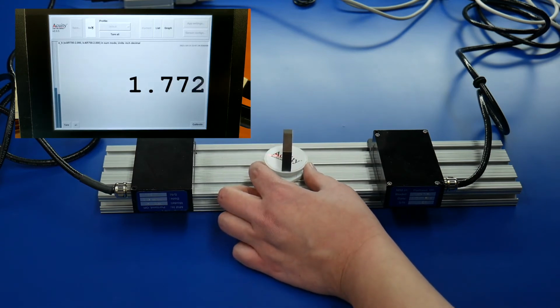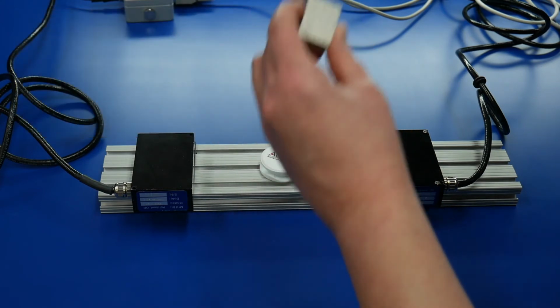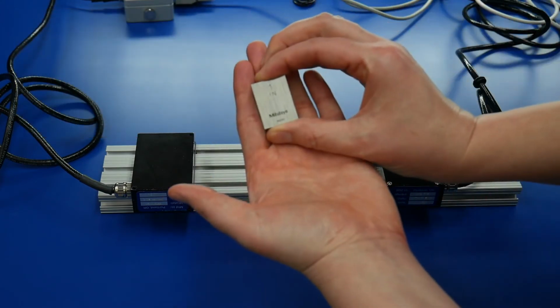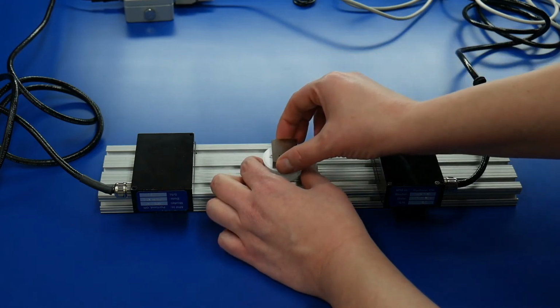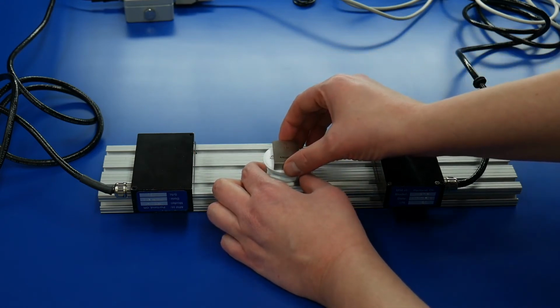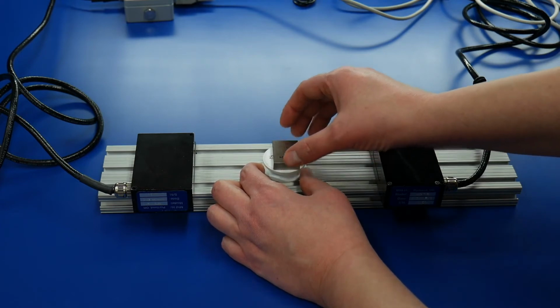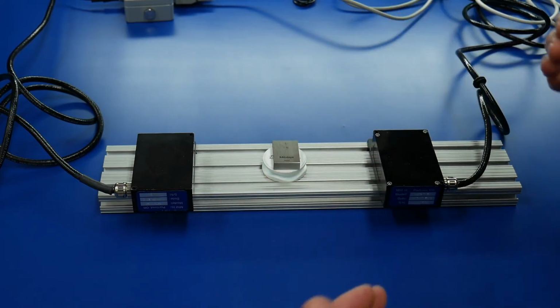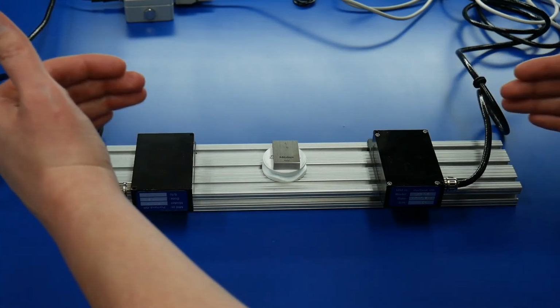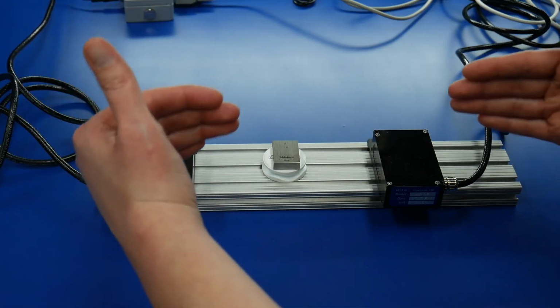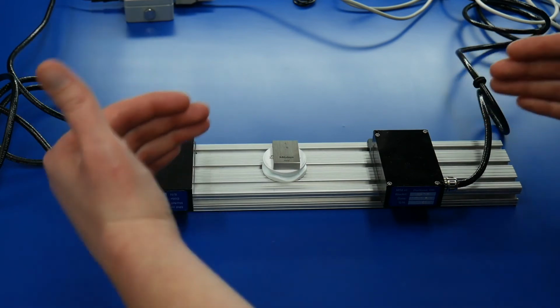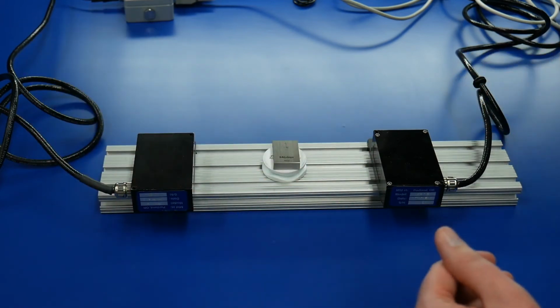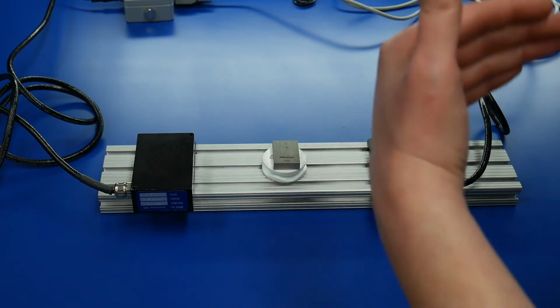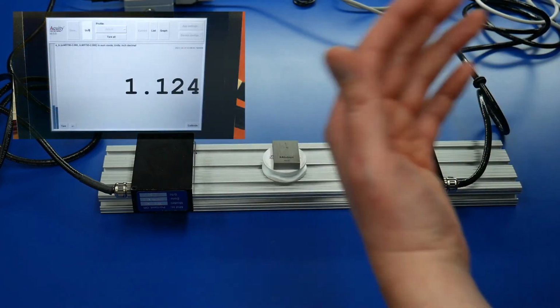I'm sorry, my fat fingers are getting in the way. Okay, so then what you're going to want to do is take a gauge block. This is a 1-inch gauge block, and you want to put it in between the two sensors. Now, you want to make sure that it is aligned so that the two laser beams are shining perpendicularly upon both sides, and that's really important. And we'll talk a little more about that in a second or two.